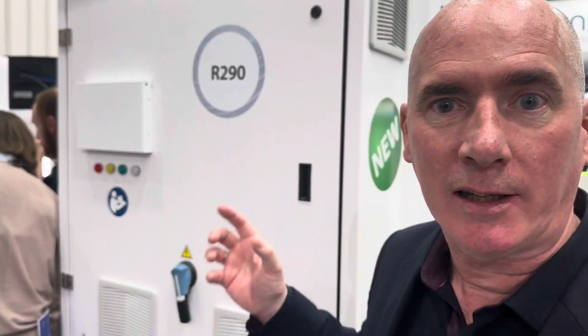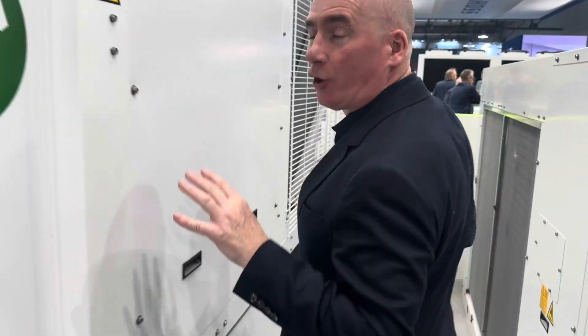Just to show you a couple of things about the propane chillers. Or heat pumps. You can have them as chillers or heat pumps. By the way, just to be aware, if it's a chiller, the efficiency is probably about 10% lower than, let's say, R32, for example. But the GWP is obviously lower, hence the reason the manufacturer is going for propane. So if you like, the direct effect, the GWP, is lower, but the indirect effect, the cost of running, is going to be slightly higher. But unfortunately, that's the way the industry is. It's all to do with the legislation, and the manufacturers are governed by the legislation. So look, it is what it is, and that's the way the market is going.